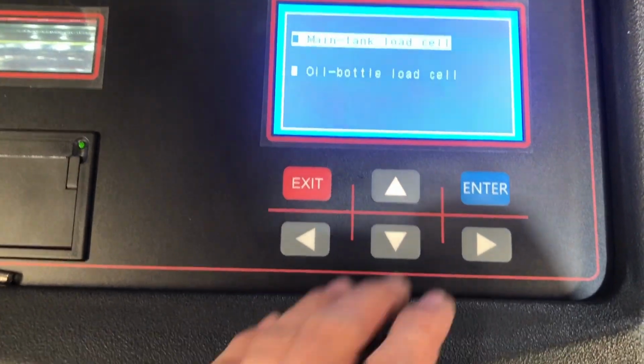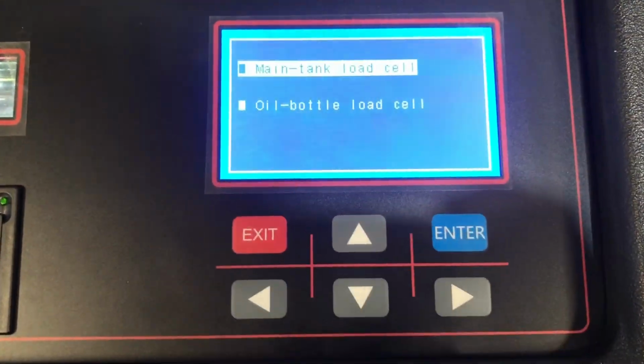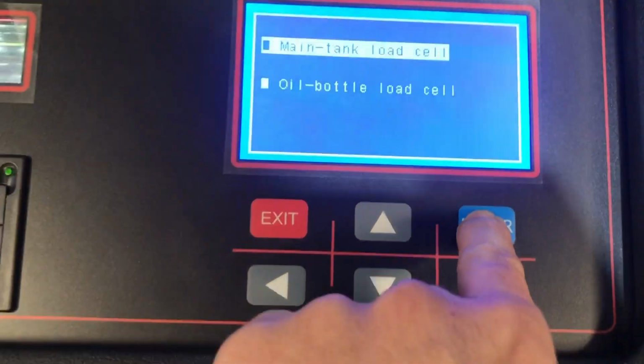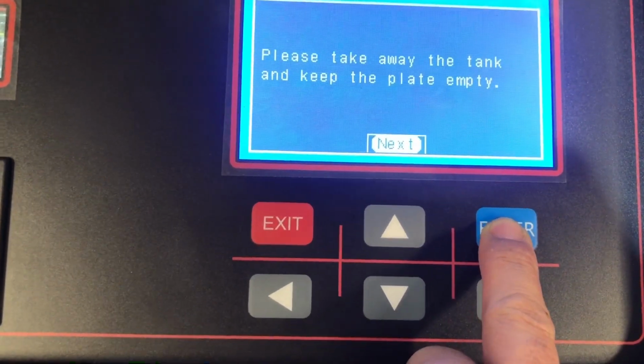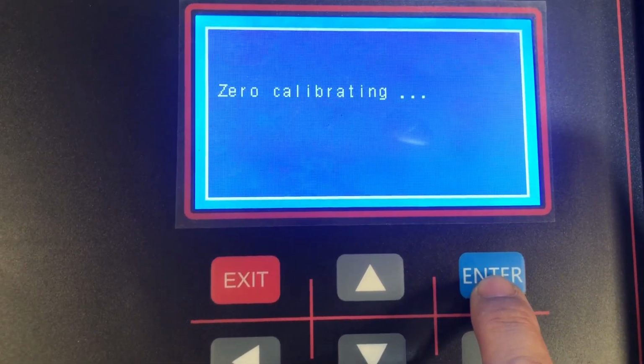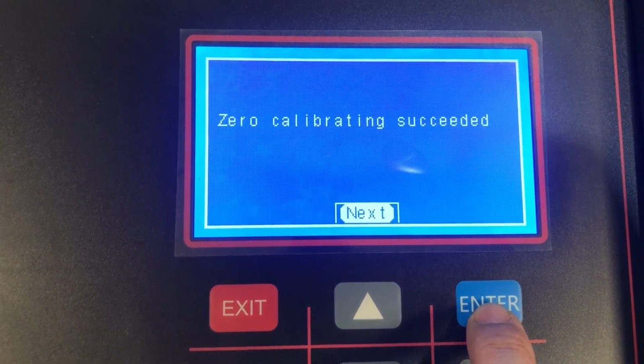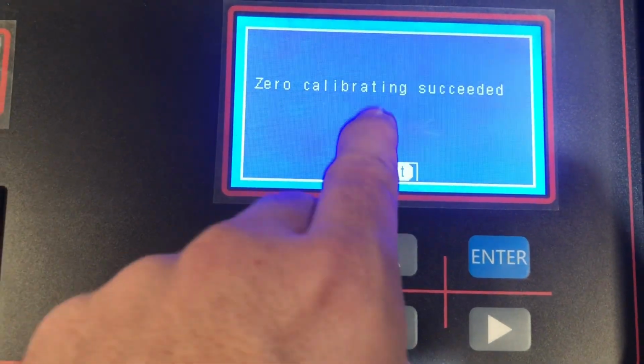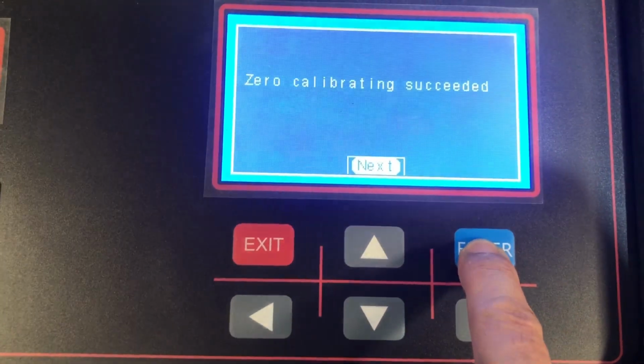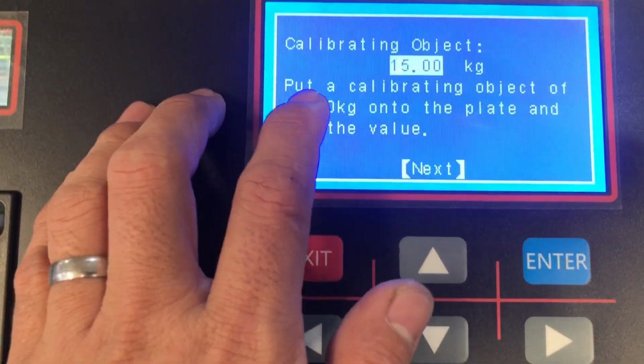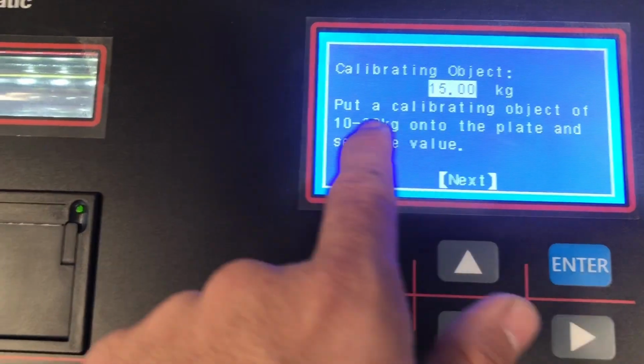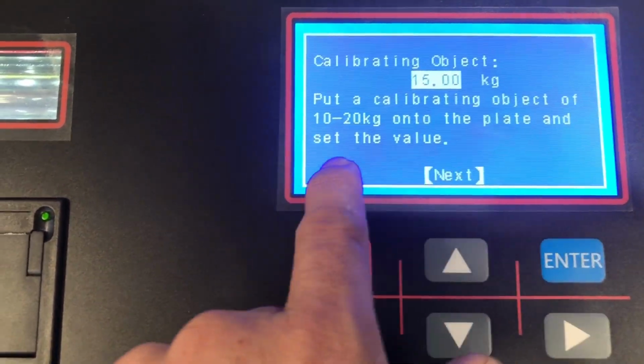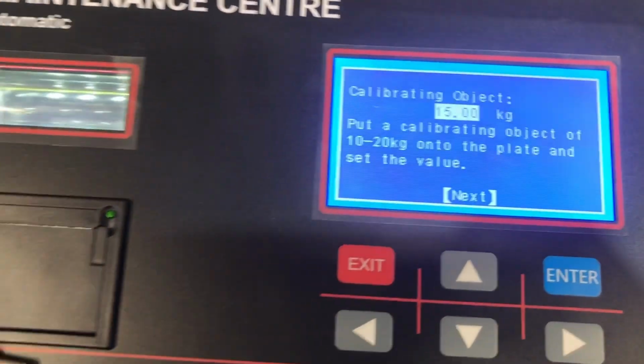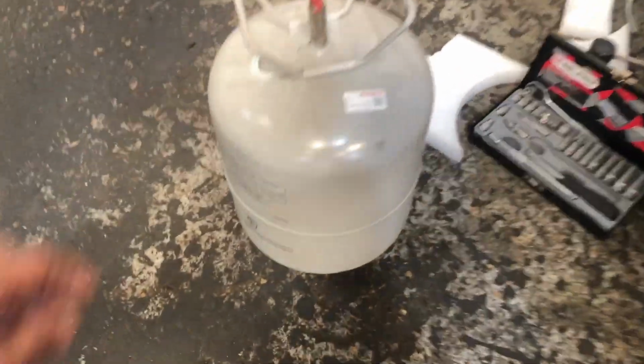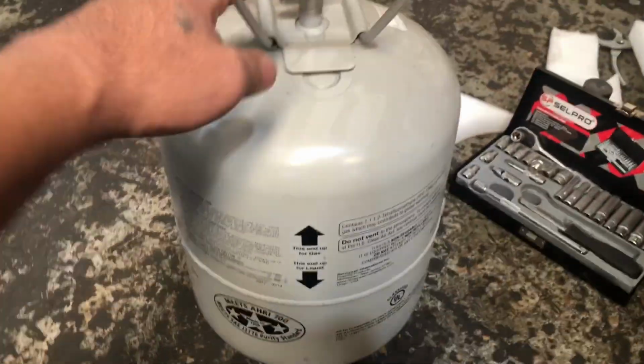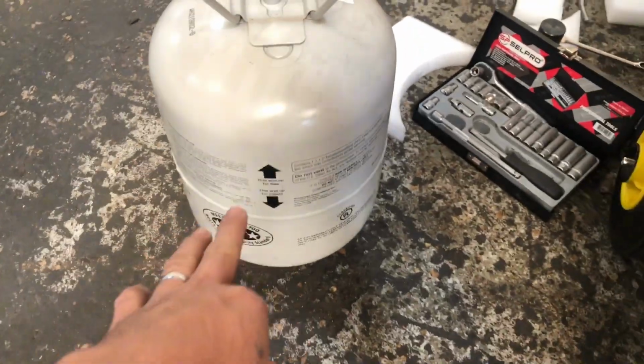After removing the tank, click this main tank load cell. Enter. Next, zero calibration, calibrating. Zero calibrating succeeded. Next. Put a calibrating object of 10 to 20 kilograms onto the plate and set the value. Now I use this temporary object, but I need to know how many kilos this is.